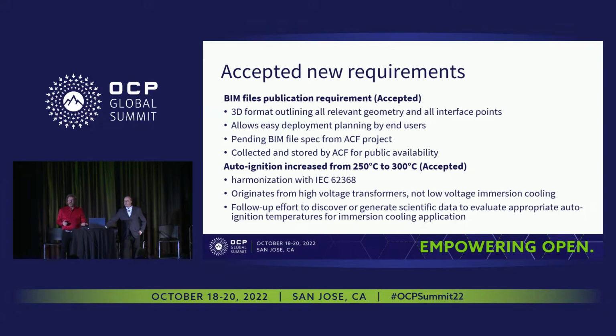The second topic is the auto-ignition temperature of the immersion fluids. Currently in the Immersion Requirements Rev 2, we've stated an auto-ignition temperature of 250 degrees C. However, there's an existing official standard within IEC, the 62368, which has been broadly discussed here in the cooling environments as well. UL will speak to that later on. That standard actually states a temperature of 300 degrees Celsius, so we're going to be harmonizing with that figure for now. There are some discussions around whether that's appropriate or not, and what it's based on.